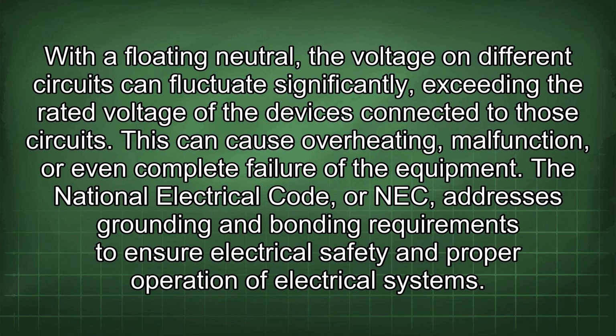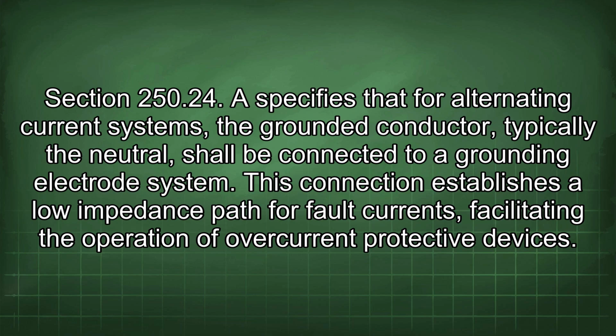The National Electrical Code, or NEC, addresses grounding and bonding requirements to ensure electrical safety and proper operation of electrical systems. Section 250.24 specifies that for alternating current systems, the grounded conductor, typically the neutral, shall be connected to a grounding electrode system. This connection establishes a low impedance path for fault currents, facilitating the operation of overcurrent protective devices.